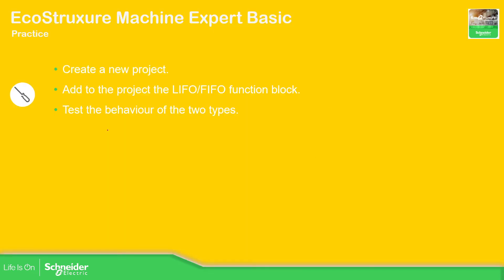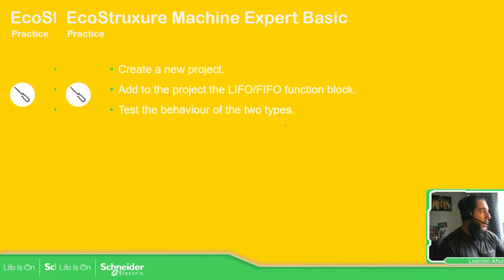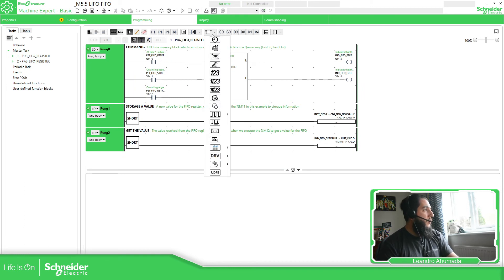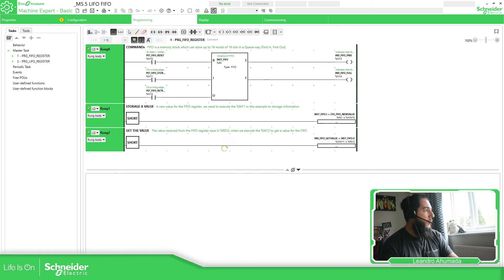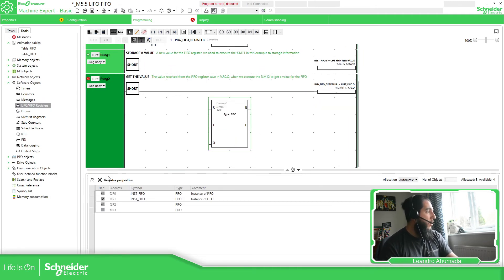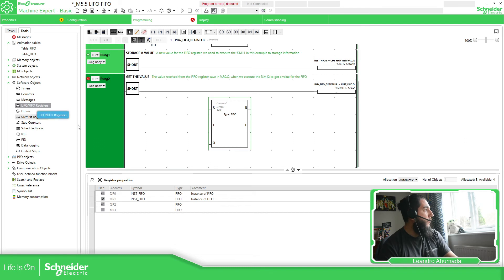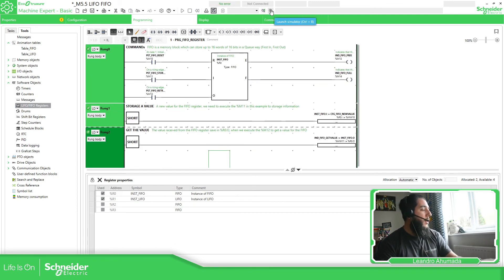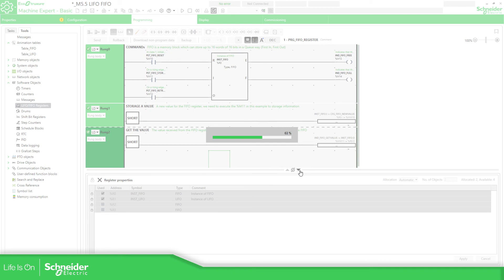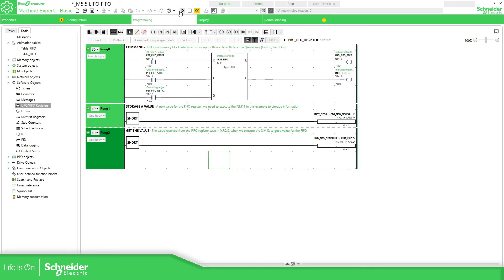What you can do is create a new project and create the logic to test both function blocks. I have made this example which is based on what you saw in the presentation. You just need to go here, select the LIFO FIFO register, select a position, and you can see you have LIFO and FIFO — it's very simple. If you double click you can access the register properties. You can also go to Tools, Software Object, LIFO FIFO Register, to see all this information. Now I'm going to compile this and show you how it works.